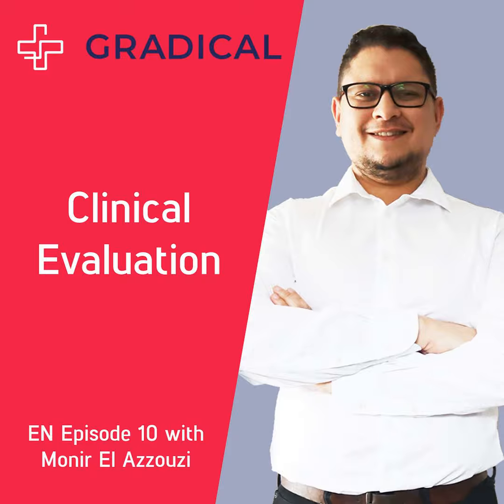So again, if we do equivalency, there are three criteria to look at. There is an MDCG guidance for that, with a table explaining how you can do equivalency. The first criterion is the technical aspect. Is the product technically the same, doing the same thing, used on the same patient, delivered the same way, etc.? The technical aspect is really important because you can say, no, technically it's different, so we don't use that. But in your case, it is technically the same. The product is the same.